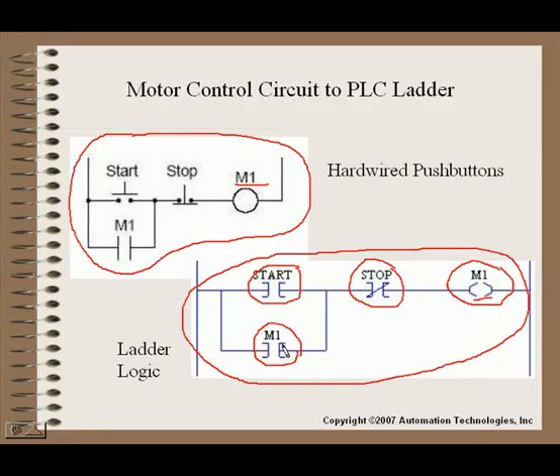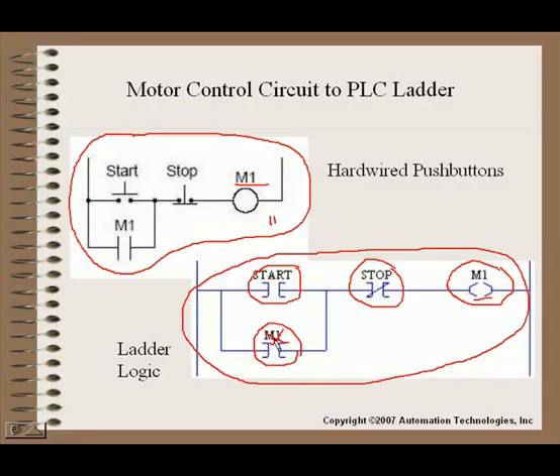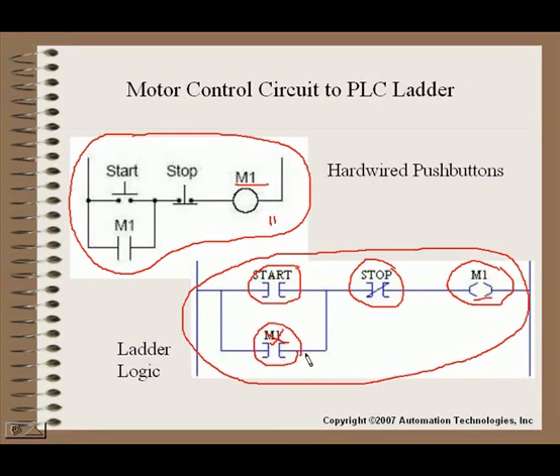Now actually, I don't like to do this. We actually like to take this relay coil, take a contact that would come back from that relay coil, and then enter that into our PLC program, and therefore we actually have a real world understanding when we seal our circuit in. If this relay were to drop out for any reason in the field, then it would also drop our seal in the program.